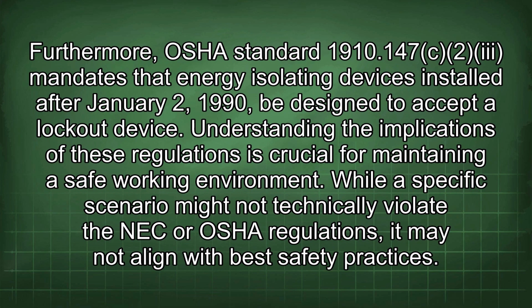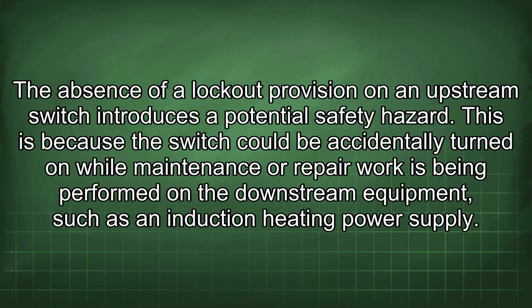While a specific scenario might not technically violate the NEC or OSHA regulations, it may not align with best safety practices. The absence of a lockout provision on an upstream switch introduces a potential safety hazard. This is because the switch could be accidentally turned on while maintenance or repair work is being performed on the downstream equipment, such as an induction heating power supply.